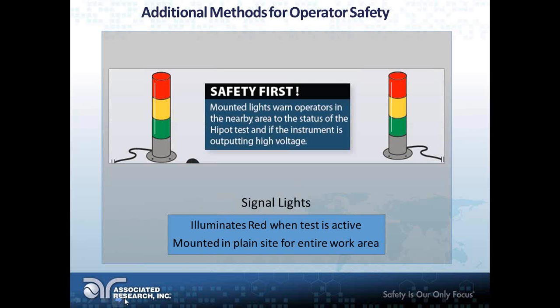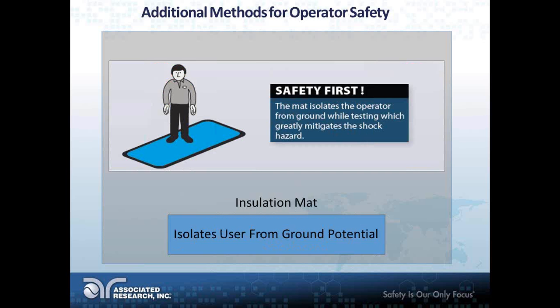Another thing you can do is the lights, as I mentioned—it illuminates red when a test is active, and it's mounted in plain sight for the entire work area. And then, of course, an insulation mat—it isolates the user from ground potential. Simply put one on the ground right by the testing station, and it will greatly mitigate your shock hazard. Just something I wanted you guys to keep in mind before we move forward.